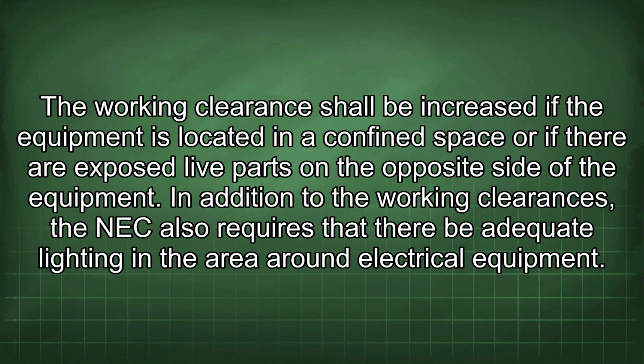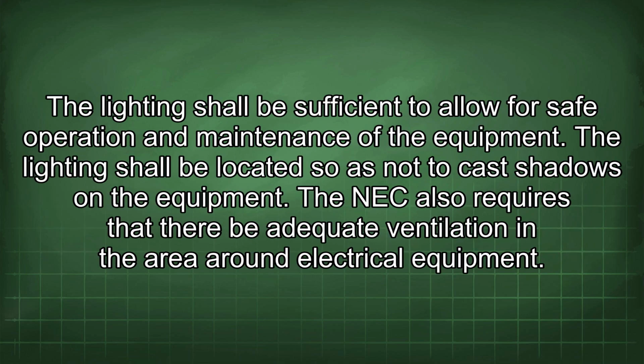The working clearance shall be increased if the equipment is located in a confined space or if there are exposed live parts on the opposite side of the equipment. In addition to the working clearances, the NEC also requires that there be adequate lighting in the area around electrical equipment. The lighting shall be sufficient to allow for safe operation and maintenance of the equipment. The lighting shall be located so as not to cast shadows on the equipment.